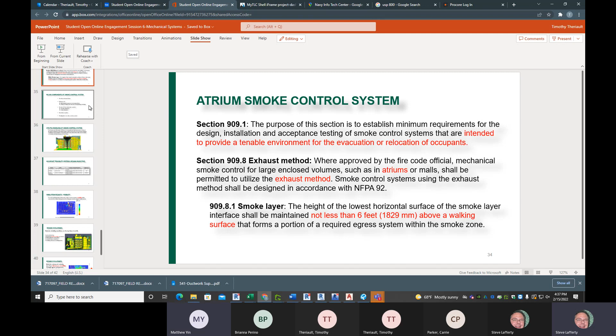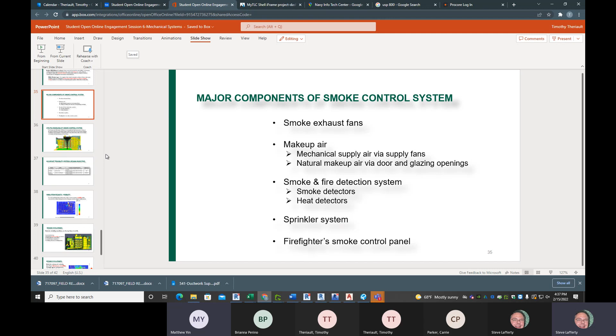And going to the next slide, this is mainly about what components will be involved in the system. So first of all, definitely the smoke exhaust fans, because that's the equipment that exhausts the hot smoke and the gases during a fire. And then why you need a makeup air: when you exhaust the air out of the building, it is depressurized, but you don't want the building to be too depressurized. That's why you want to introduce air in to compensate for the air being exhausted, so that you are achieving a dynamic balance condition in terms of pressure. And that's why you need makeup air.